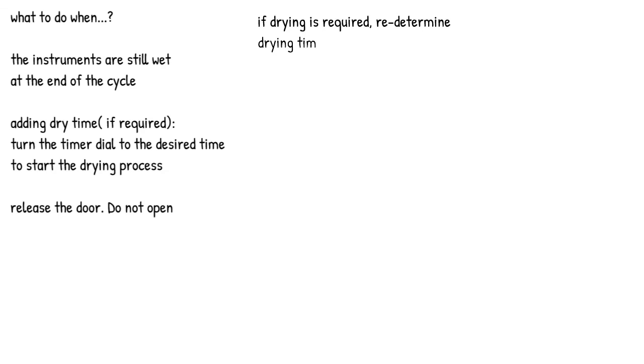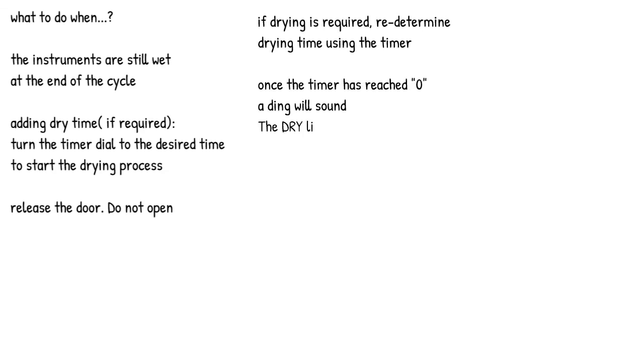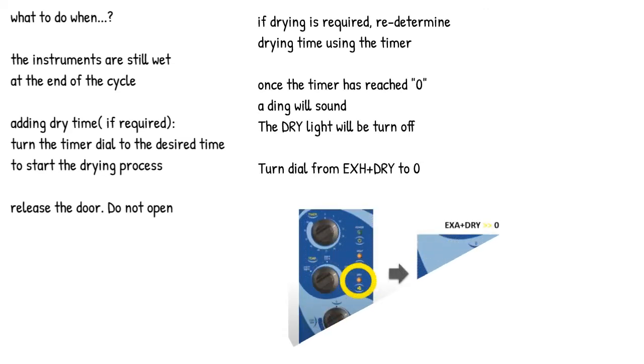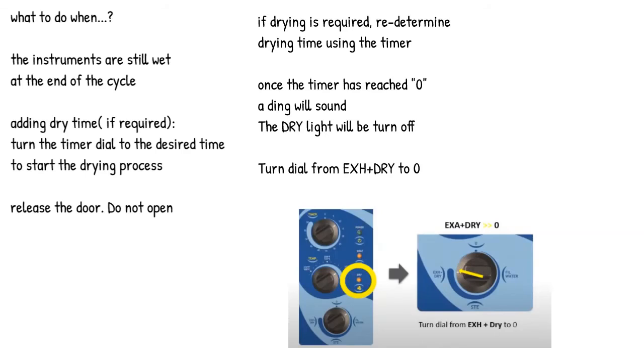What to do when the instruments are still wet at the end of the cycle. Adding dry time: if required, turn the timer dial to the desired time to start the drying process. Release the door. Do not open. If drying is required, redetermine the drying time using the timer. Once the timer has reached 0, a ding will sound. The dry light will be off. Turn the dial from EXH plus dry to 0.